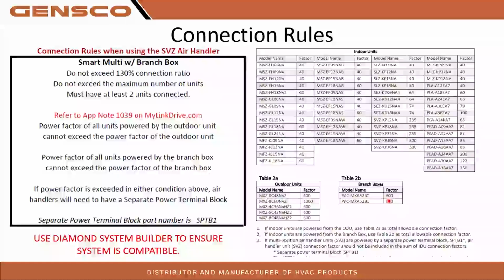So if you're questioning how close you are to that power factor, you can use this chart found on MyLink Drive. Just go through, look for the equipment or the closest generation to what you may have, use the power factor right there, and make sure that you're under 600. If you go over 600, a separate power terminal block is what you're going to need.